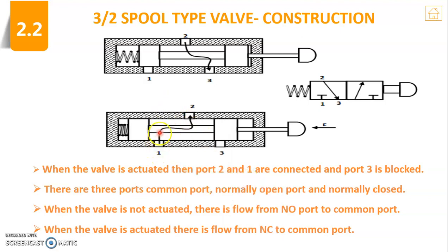Due to that, you can see that your input will flow through this path and it is going to reach your output where the actuation is going to happen. At the same time, your pressured air will not be sent out, so that you are closing the vent by using the next spool, which is the next sliding spool. By this construction you can make this valve a 3x2 spool type direction control valve. You are controlling the input and output direction by using this type of construction.